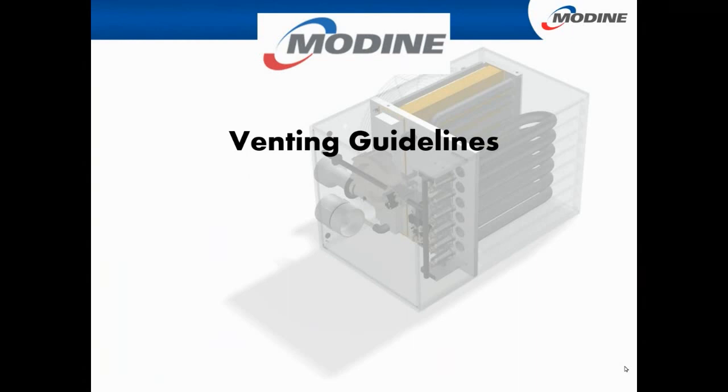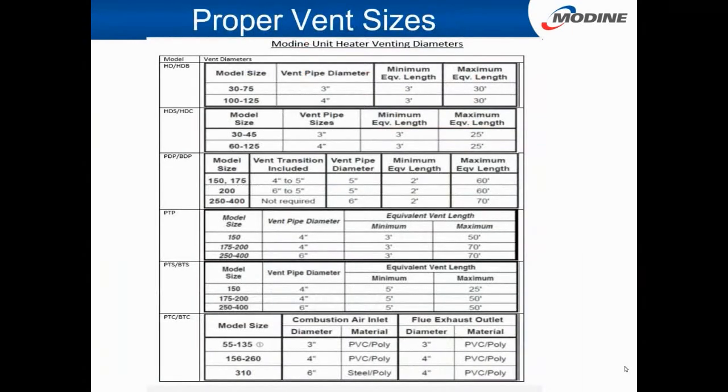Venting guidelines. I'm going to cover these, and I've told these for many years, right? Everybody calls me and says it says 3-inch vent pipe, I go to 4, all these different things. In the last couple of days, I've read the installation instructions multiple times just to try to figure out what those issues would be. I think Randy will cover derating them, and I'll cover some stuff in venting that I think will help too. Because you hear everybody saying the limit switch is going out. I heard it all the time when I was over there. Call me on my limit switch, I had to go to 4-inch vent pipe. Okay. You can't really tell contractors all the time, you have to suggest, it's not what it is. But we'll talk about that here.